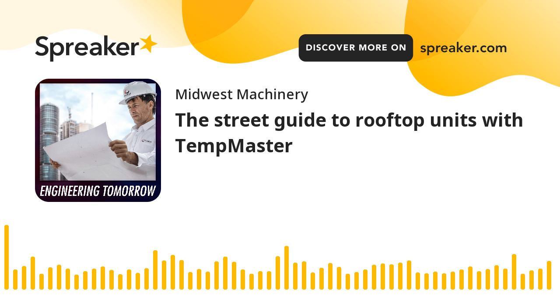That's great. So we've got it installed. It's easy to service. What are you guys doing for peace of mind, redundancy, and reliability? How are you keeping this running? Well, first of all, for peace of mind, the supply fan being a direct drive fan and not having a belt, that's another point that's not going to fail. If a belt fails, it can shred up and get into the airstream, and I have to come up there and replace it. It's something you have to check on more often, making sure your belts are staying tight and not getting shredded. Just like a belt in your car, those fail more often than the components around them. So with the direct drive fan, you don't have to worry about the belt.